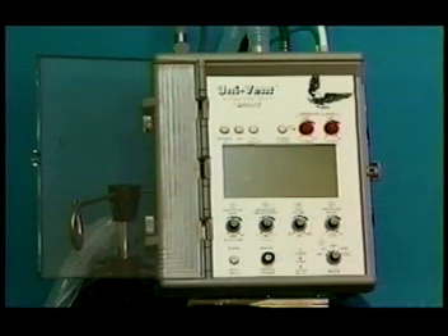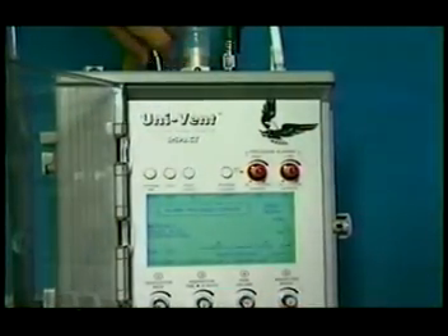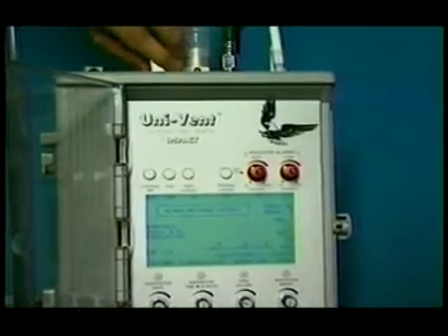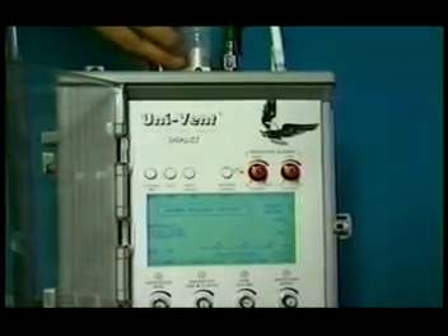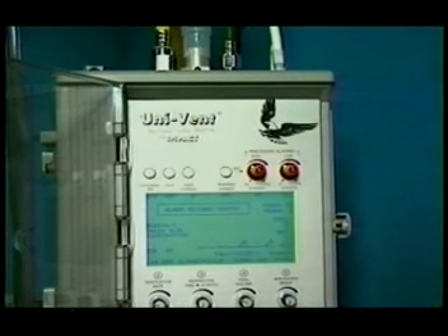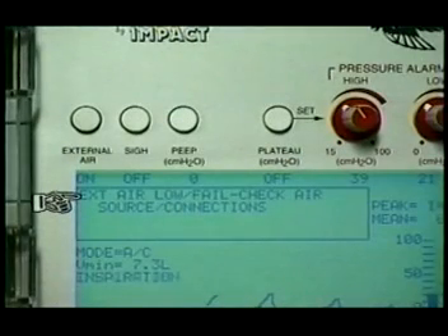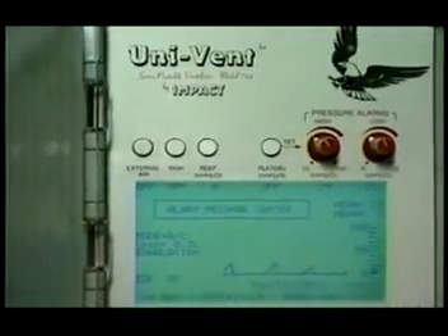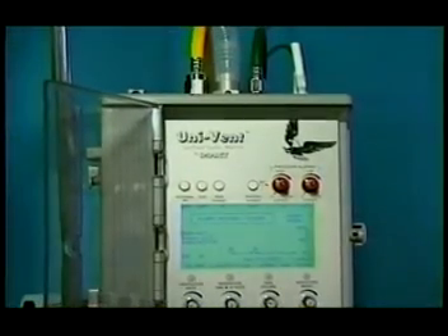The ventilator will automatically operate from external air if 50 psi external air is connected when the ventilator is turned on. External air is connected by attaching the yellow air hose provided to the fitting labeled air in and a 50 psi medical grade air source. If external air is connected during operation, it may be utilized by pressing the external air push button to on. If you try to turn external air on and none is connected, it will trigger the external air low fail alarm. There is no way to eliminate this alarm except by pressing the external air push button to off or by connecting external air having sufficient pressure.